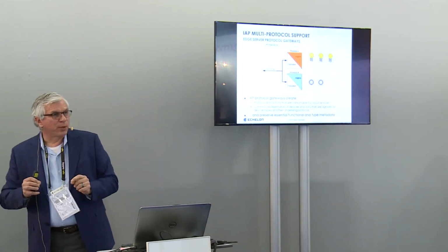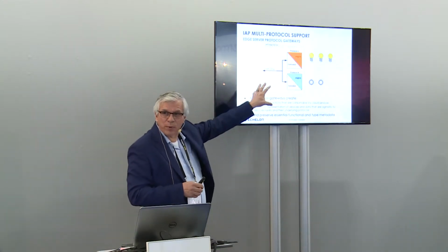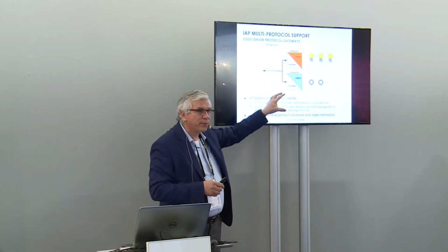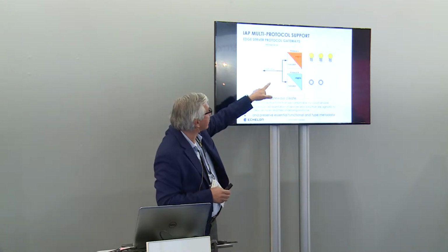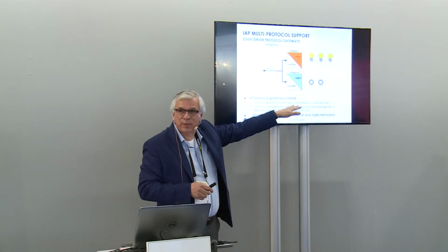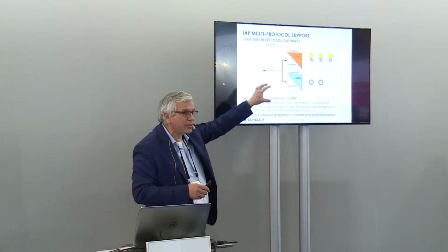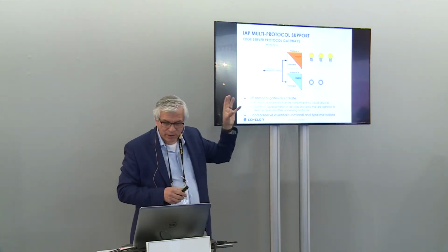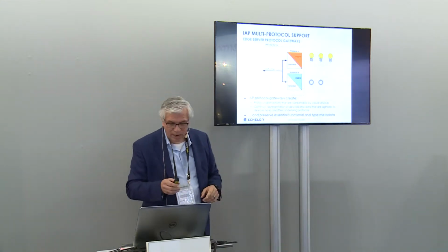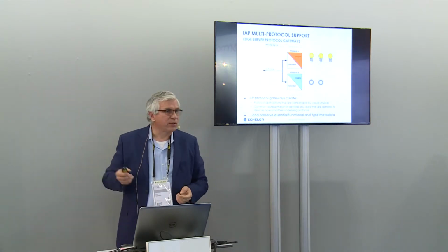And the beauty of the approach is it's inherently multi-protocol. Right, so here's IAP-MQ. So this is the open protocol for MQTT. I can have different protocol translators that translate from MQTT to other protocols. So for example, that top one might be LON-based lighting controllers. The bottom one might be Modbus-based motion sensors. And just by having two simple translators and engines, I can interface with all those devices. So those gateways can create the abstractions of those different kinds of devices and bring them up into the cloud services that you're connecting to.